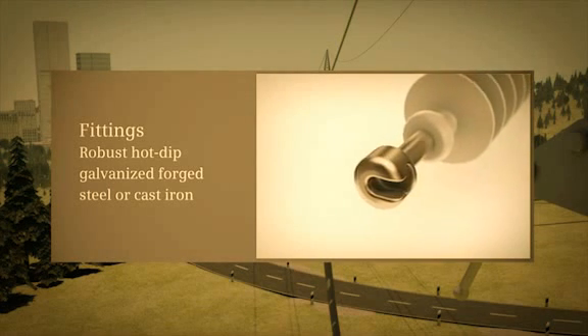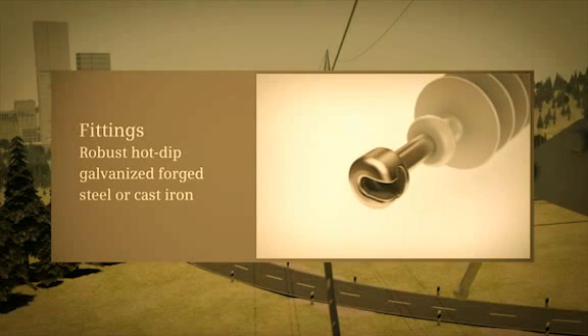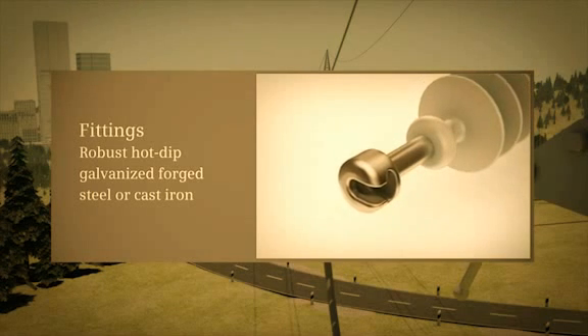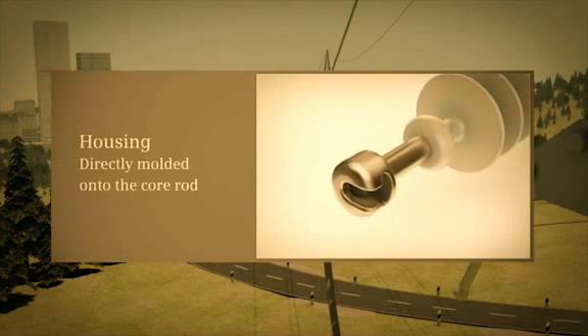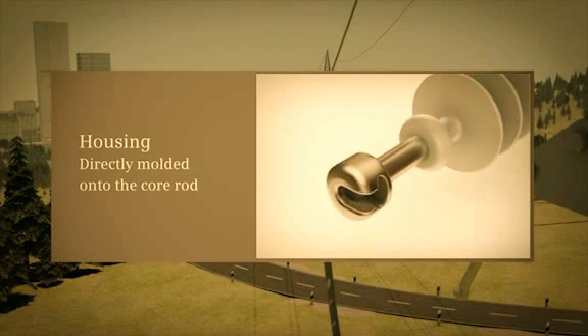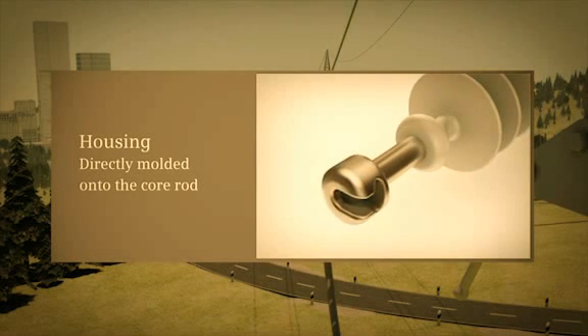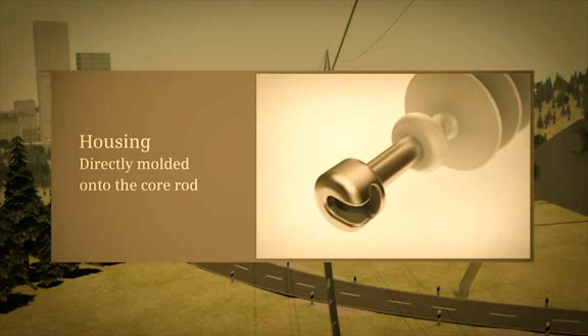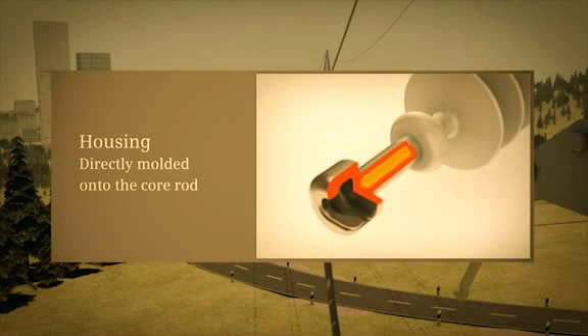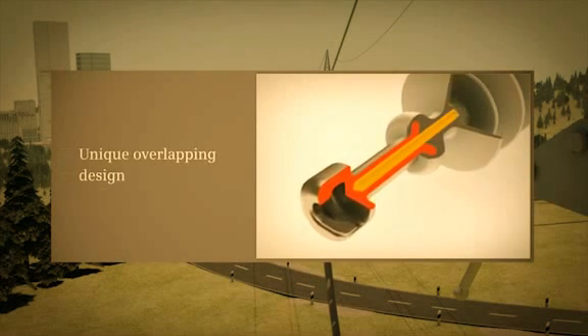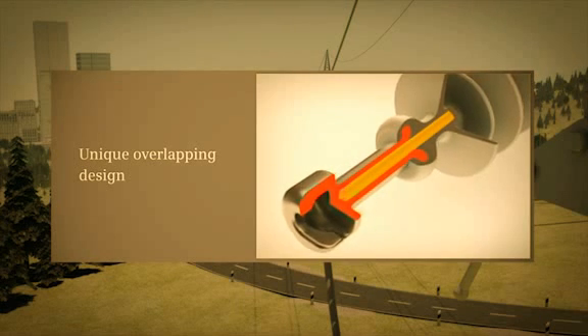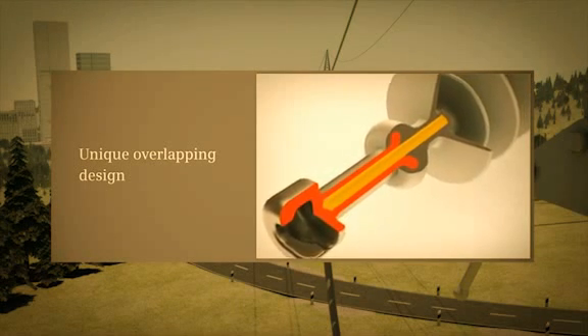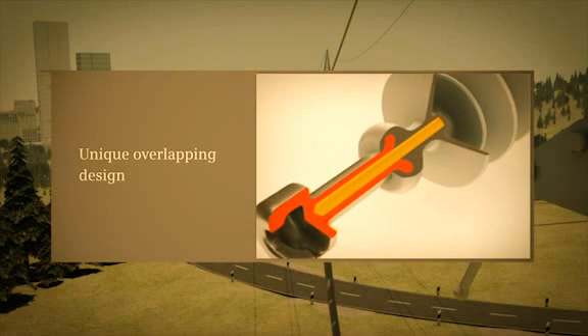The most sensitive part of a silicone insulator is its junction zone. To minimize insulator sensitivity and further improve robustness, the HTV silicone housing of Siemens 3FL silicone long rod insulators is directly molded onto the core rod. The sensitive triple junction point, where the FRP rod, the end fittings, and the silicone housing all conjoin, is overlapped by the housing.